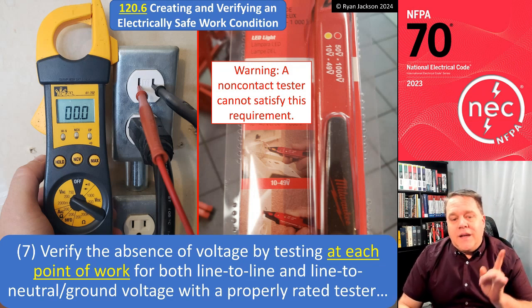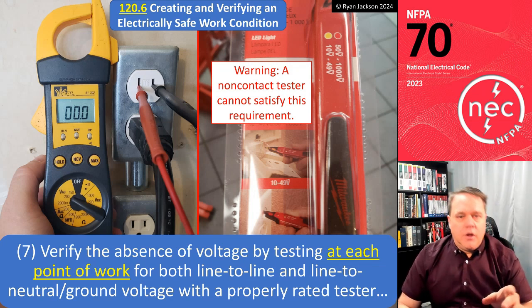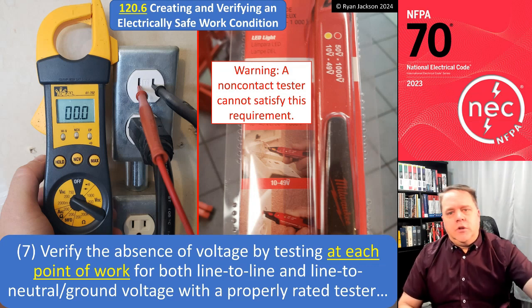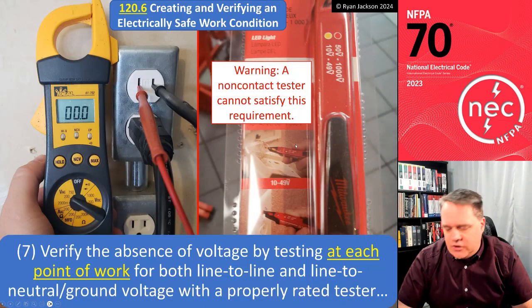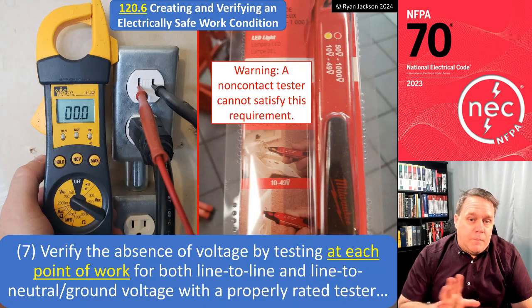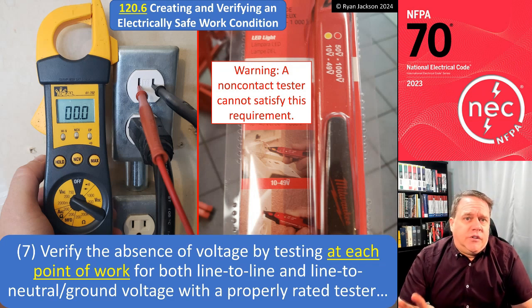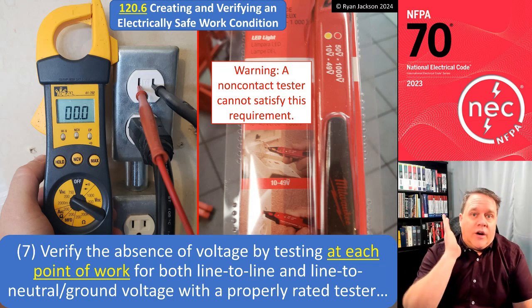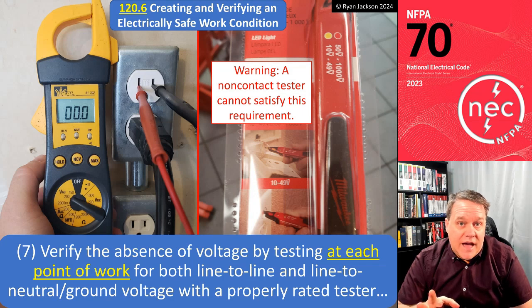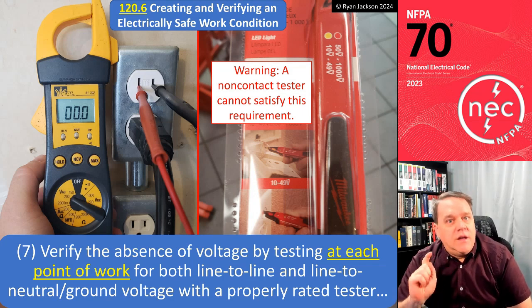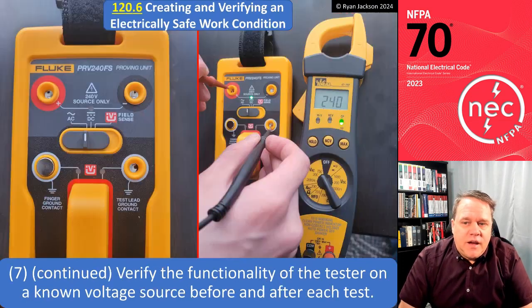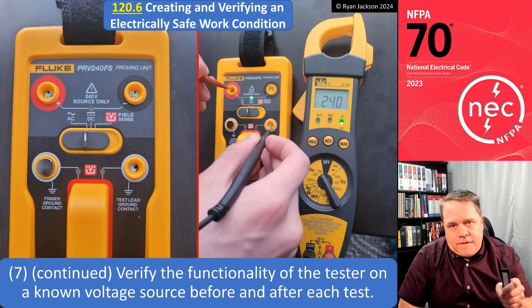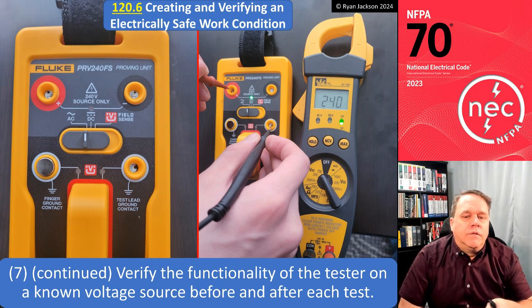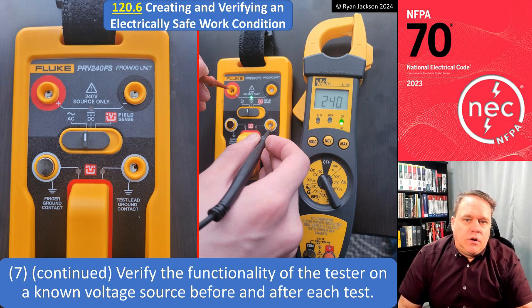Test it line to line and line to neutral or line to ground, which of course is why you can't use a proximity tester like this. If you're using a little hot stick like this, a proximity tester, those have their uses, but creating and verifying an electrically safe work condition is not one of their uses. Those just give you a little bit of information. When we're actually testing to verify the absence of voltage, we need to test it line to line and line to neutral with a properly rated tester, and we need to verify the functionality of the tester on a known voltage source before and after each test.